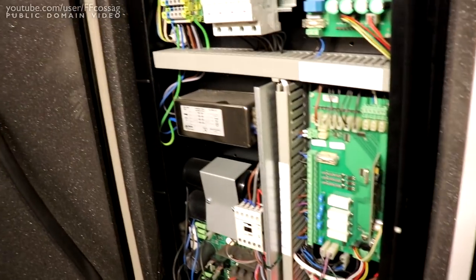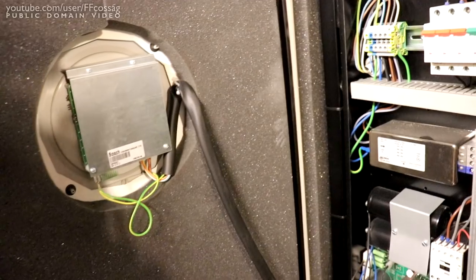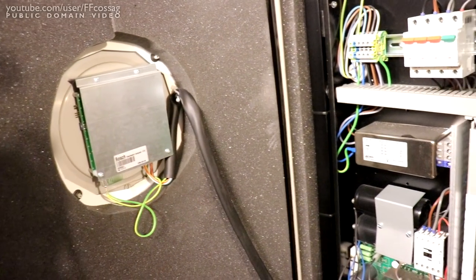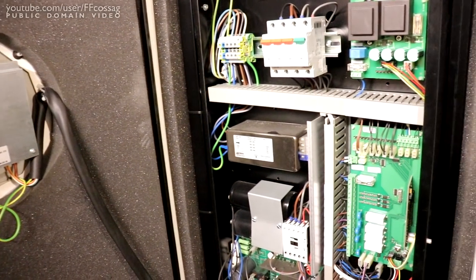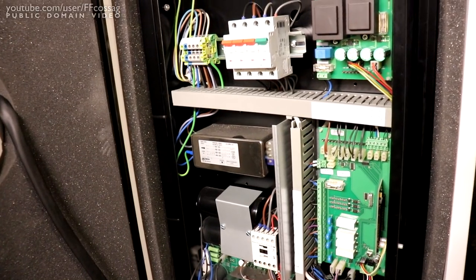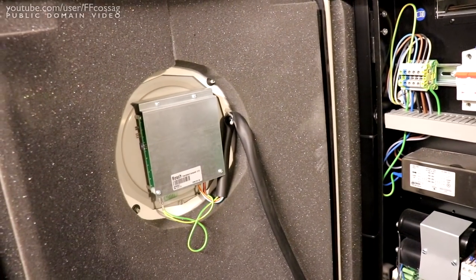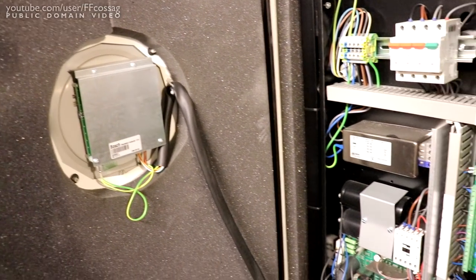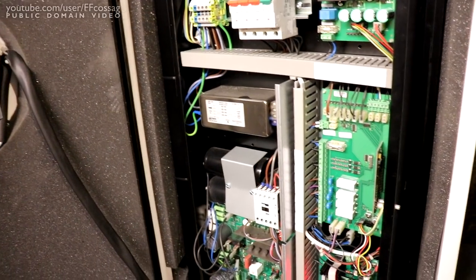So it was throwing an alarm on the front panel of A80. Was it a low voltage during compressor start and it just wouldn't do anything. So what we know is we have brain activity because the front panel lights up just fine but it won't create any heat, it won't run any circulation pumps.